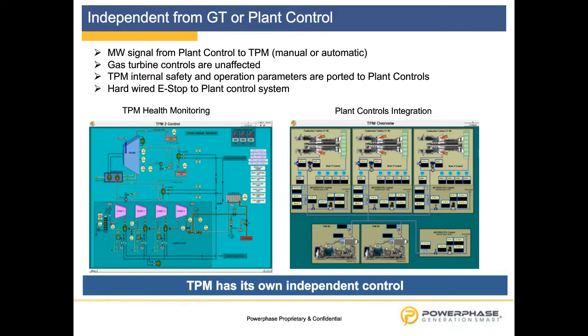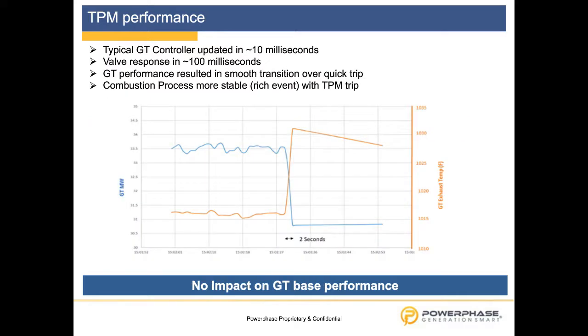Many questions are, for example, what happens if the Turbophase module trips? What I have here is a typical operational pattern. You see on the right side the exhaust gas temperature, and on the left side the gas turbine power. The gas turbine power, the blue line, is around 33.5 megawatt, which is the equivalent on the 6B. And what happened is that we tripped the Turbophase module on purpose.